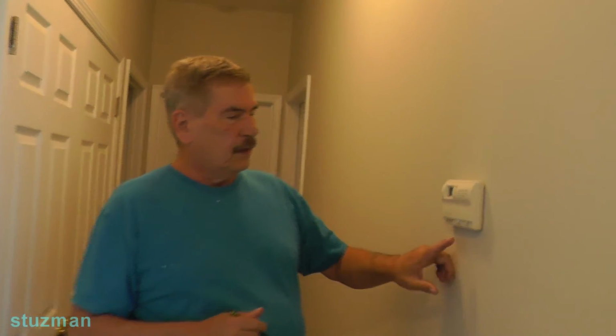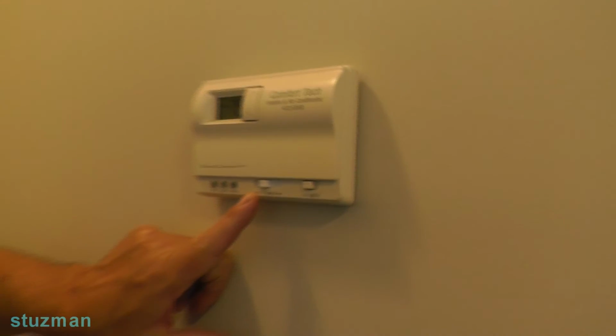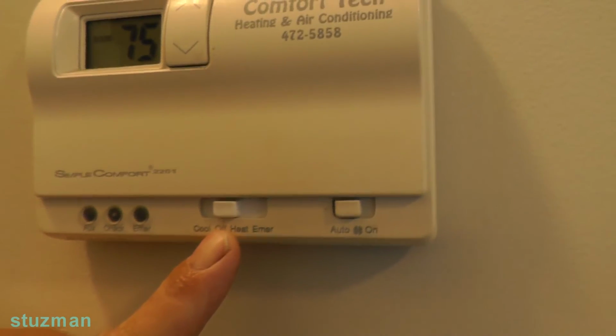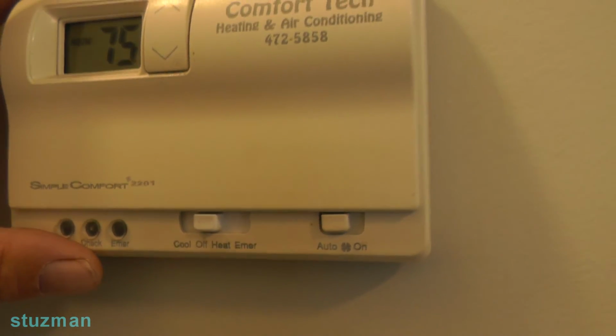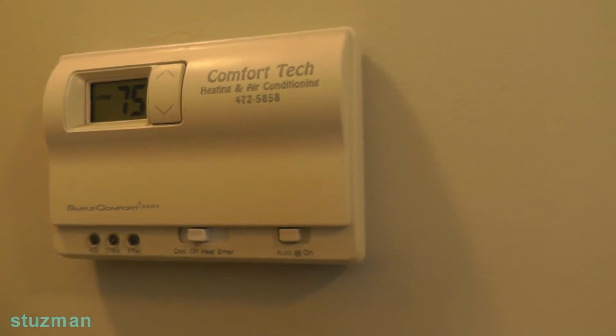Now, the first thing I'm going to show you is the method where we power the unit down. What I like to do is turn off the thermostat - I've already turned it off. It was in cool, and now I have it in off. This will turn off the contactor. It's not a necessary thing because we have a disconnect outside, which we're going to do too.